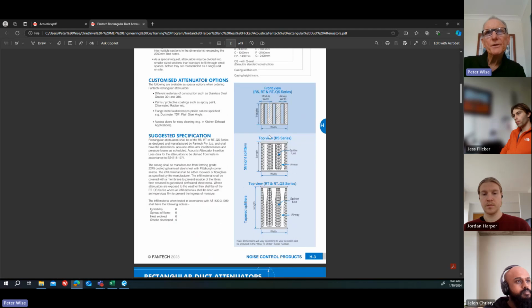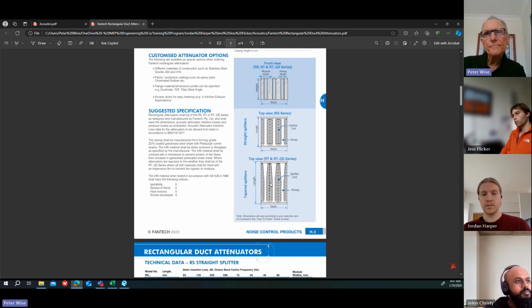So you can see from these diagrams the RS model has got the splitters straight all the way through. They've got a bit of a bull nose at the entrance, so the air's coming this way, a bull nose at the entrance and then straight. The RT has got a tapered splitter at the exit, and that reduces the pressure loss as the air leaves the attenuator. The RT type is the one that we would use more commonly. The RS has a superior attenuation or insertion loss performance, but the pressure drop is higher. They're more expensive. The RT is the most commonly used one in the rectangular type.